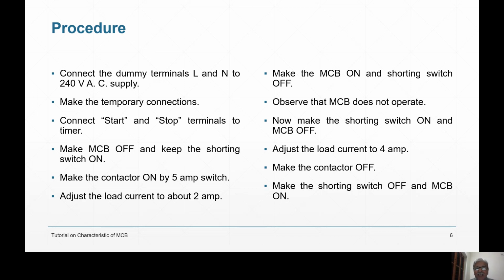Then obviously the parts inside the MCB are not at normal temperature. They are not at room temperature; otherwise, they are at room temperature. The main device on which the MCB works is a bimetal strip, made of two different metals having different coefficients of expansion with heat. That means when they are heated, they will expand separately. One will expand by 4 centimeter, another by 4.4 centimeter. But they are welded together, so when they expand, they will have to bend. And the bending of the bimetallic strip is used as a mechanical latch to trip. So the tripping mechanism is connected with the bimetal strip.